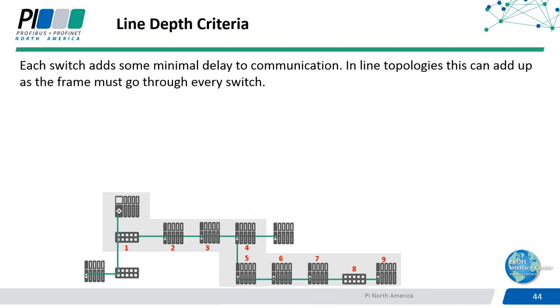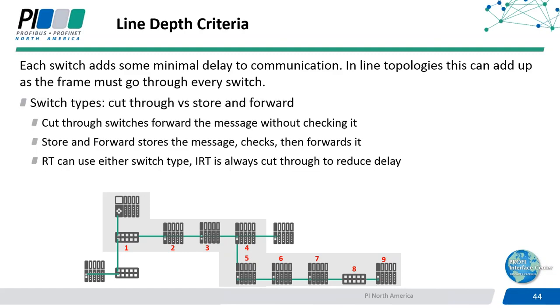So we want to talk about that. Each switch in your network adds a minimum delay to the communication, and with line topologies, that can add up as the frame has to go through every switch. We have two main industrial switch types: cut-through and store-and-forward. It's up to the vendor which one you have. PROFINET RT can use either switch type, but IRT is always cut-through. Cut-through switches forward the message on through without checking it until it gets to the end node. Store-and-forward will store the message, check it, and then forward it, so it's a little slower than cut-through.